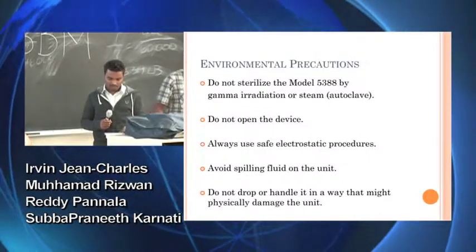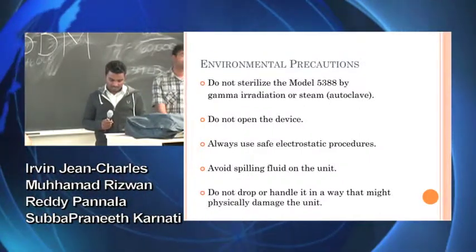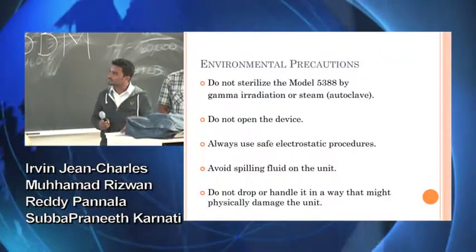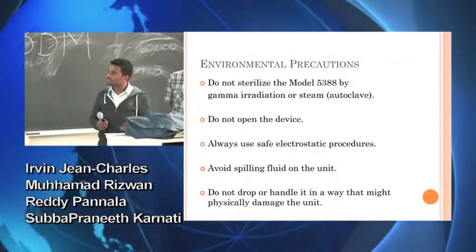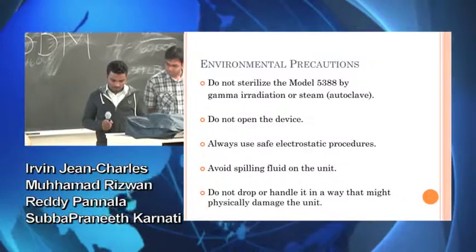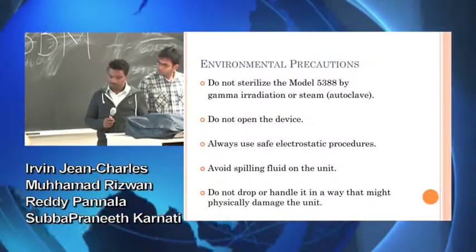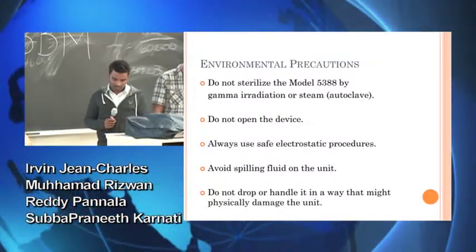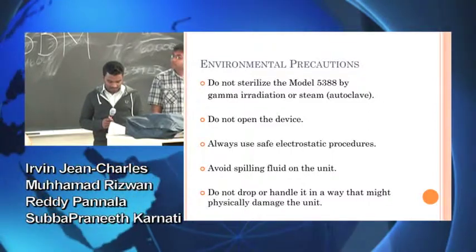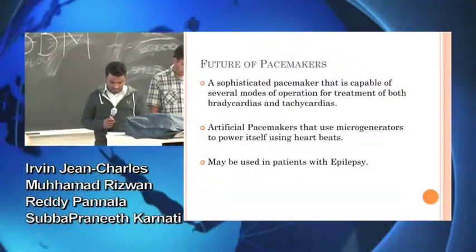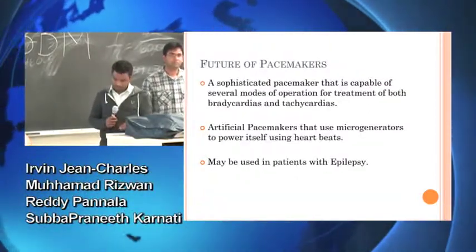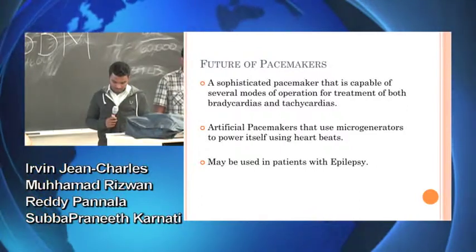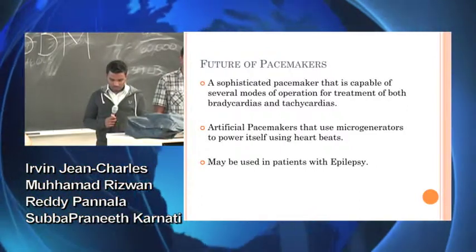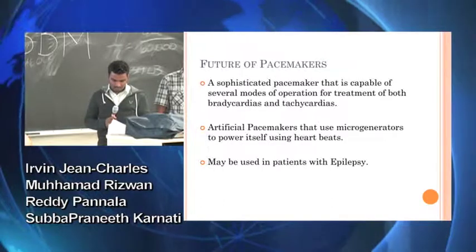Environmental precautions: one should be very careful while handling it, and spilling fluid on the machine or the pacemaker is not recommended, and it may act differently in different situations depending on the temperatures. And the adverse effect of this, if it is not controlled well, is a chance of getting a condition called tachycardia or asystole.